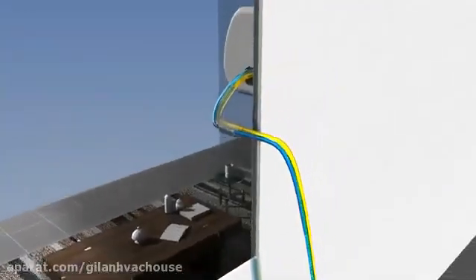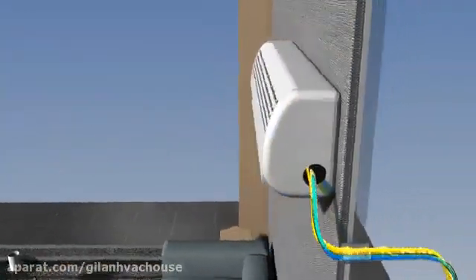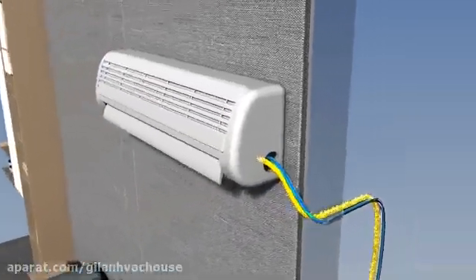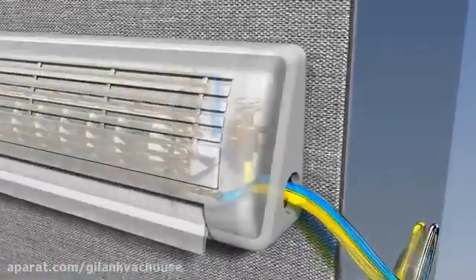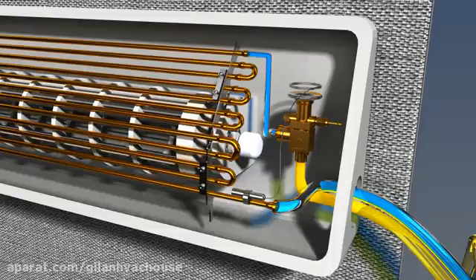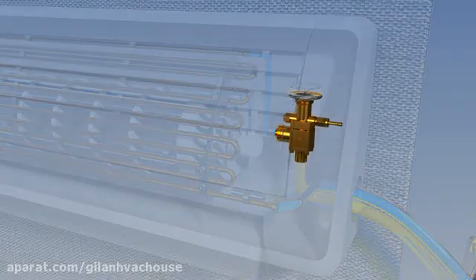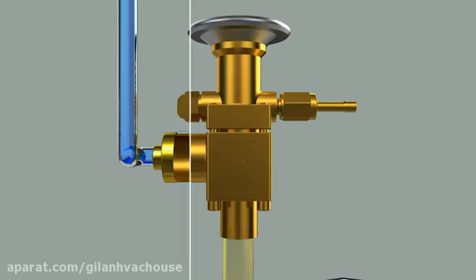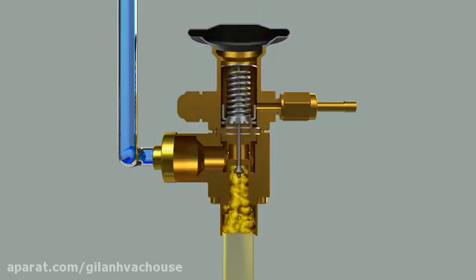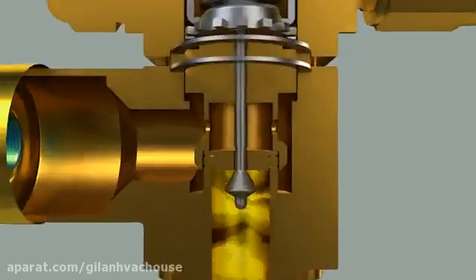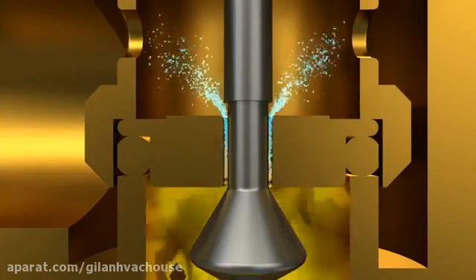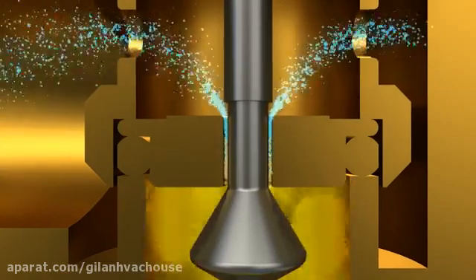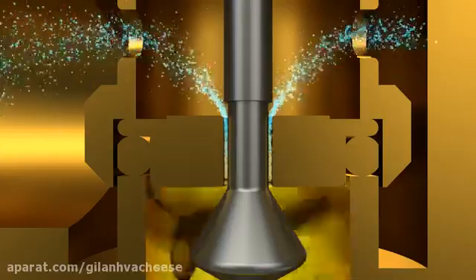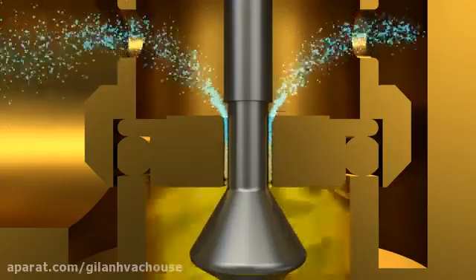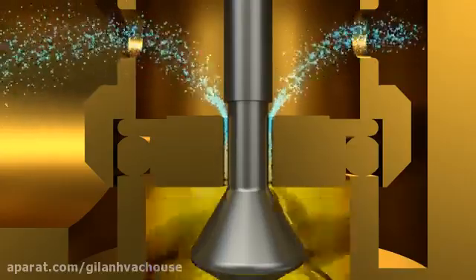Although the refrigerant has thrown off some of the heat as it passes through a condenser, it is still hot, with a temperature of about 50 Celsius. The refrigerant in high temperature and high pressure liquid flows into the expansion valve. The refrigerant which used to flow in large space now passes through a narrow area, and its pressure drops as it goes. When the pressure drops, temperature drops dramatically as well. The cool refrigerant is now sent to an evaporator.